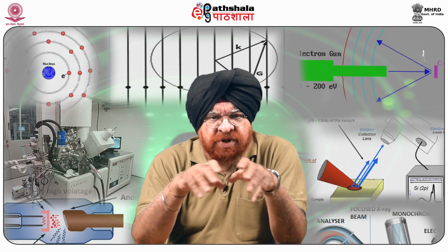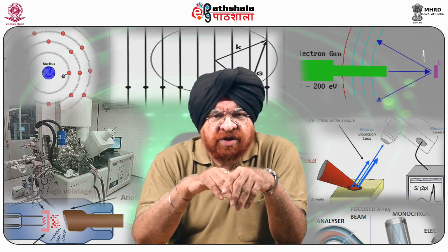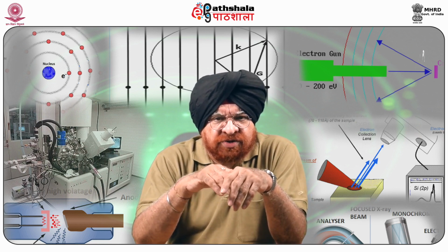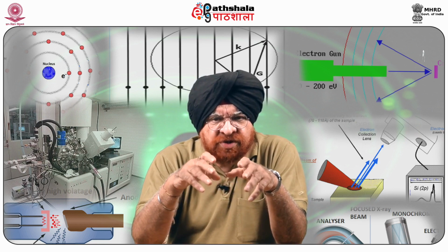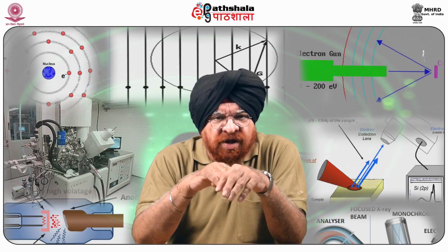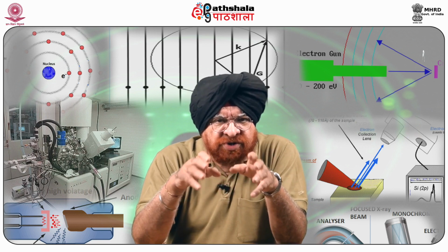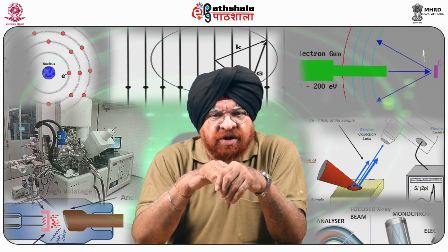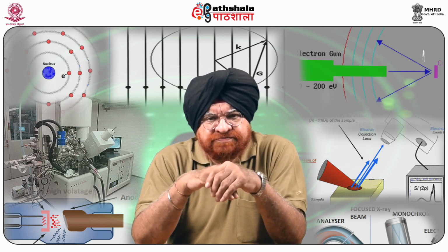It results in a pulse of approximately 10^8 electrons, which gets combined with a fluorescent screen, and the resulting signal is recorded in a fluorescent detector.